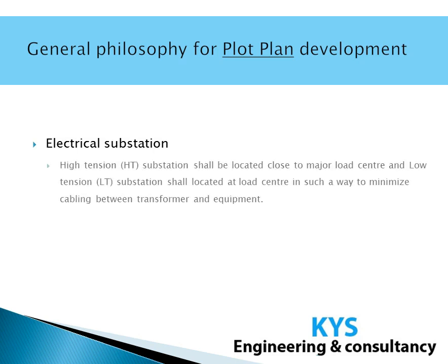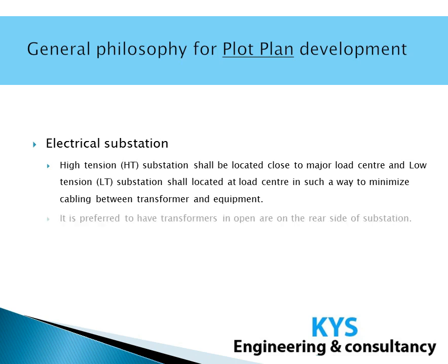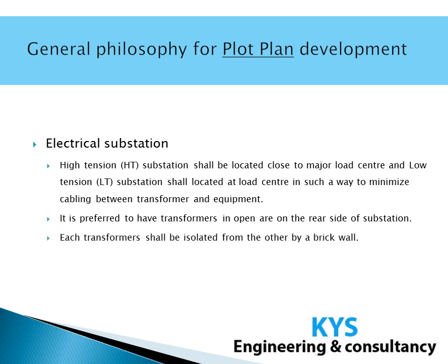Electrical substation. High tension substation shall be located close to the major load centers, and low tension substation shall be located at the load center in such a way as to minimize the cabling between transformer and equipment. It is preferred to have transformers in open area and on the rear side of the substation, and each transformer shall be isolated from the other by a brick wall.